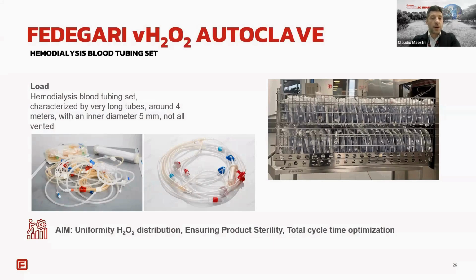Using H2O2 deep vacuum, we achieve uniform distribution, full sterility, and a total cycle time lower than 8 hours, even with that high complexity and without quarantine need. That's far shorter than an EtO process, which can take multiple days due to the aeration. On the right is the prototype built and available here in Fedegari, in our tech center in Italy, where we perform all these studies.